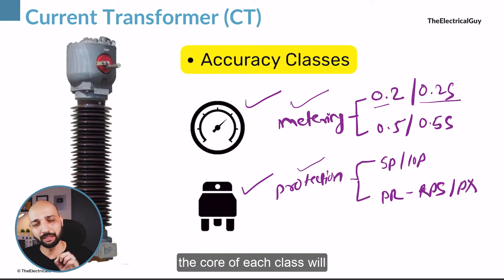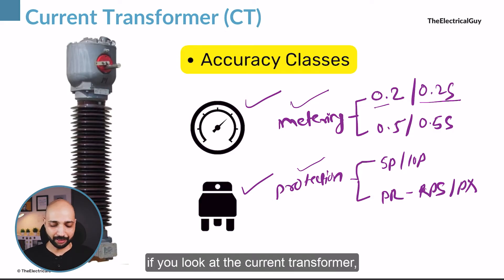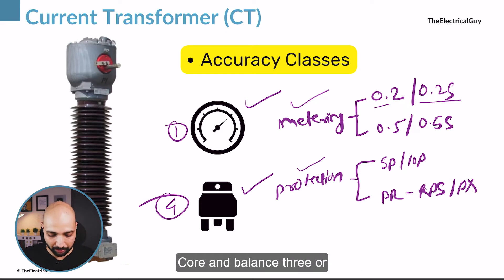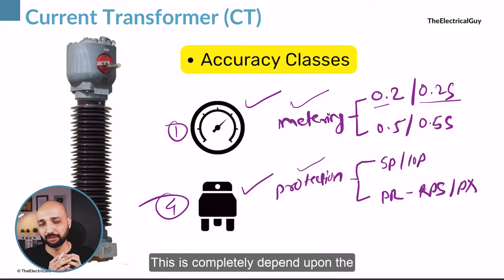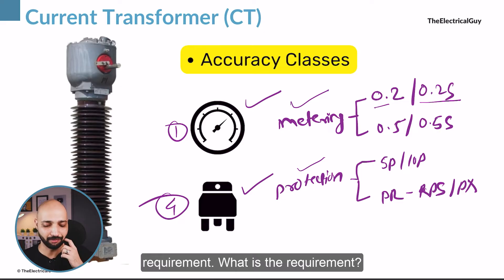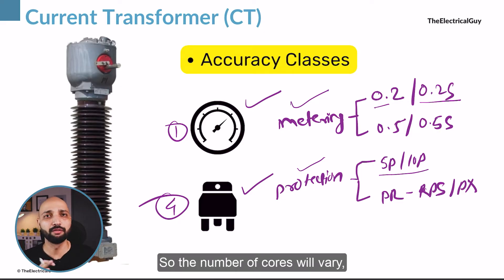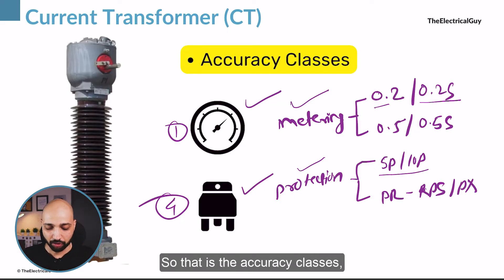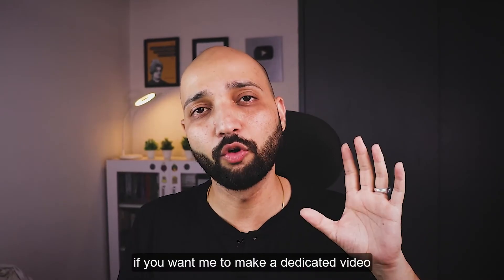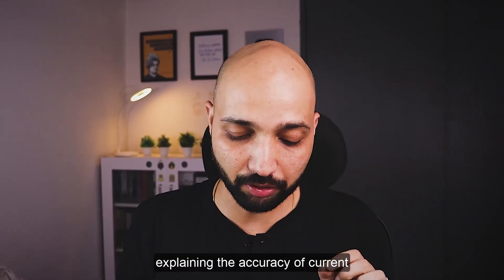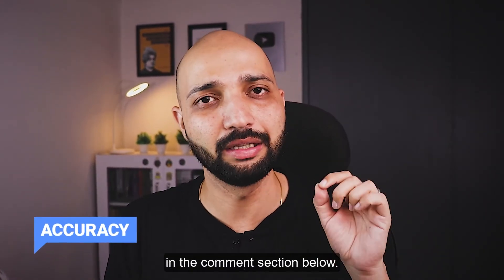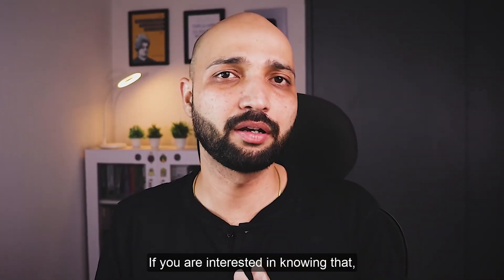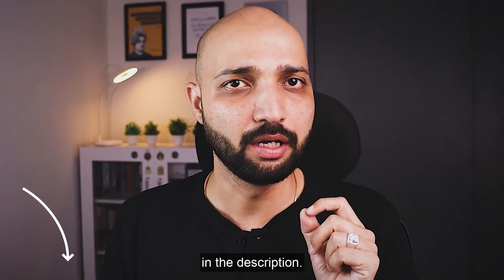For the protection core, the classes are 5P, 10P, PS, and PX. Each core of the CT will be dedicated to either metering or protection. A current transformer can have one or two metering cores and three or four protection cores depending on the requirement — generally ranging from two to six cores in total.